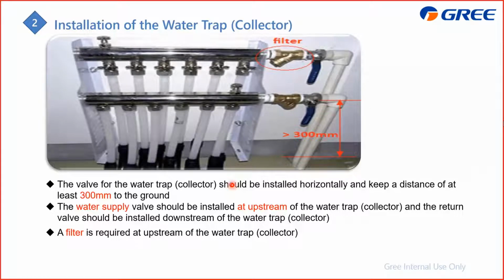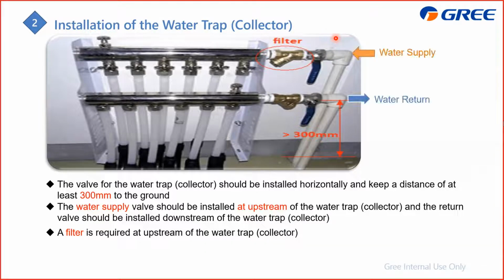And as for the installation, this is the floor coil reformer, also called the water trap or the collector. From this one, here is the water supply, and here is the water return. For this one, we also need to install this filter to ensure the water quality. And the water supply should be upstream, and the total distance to the ground should be at least 300 millimeters.